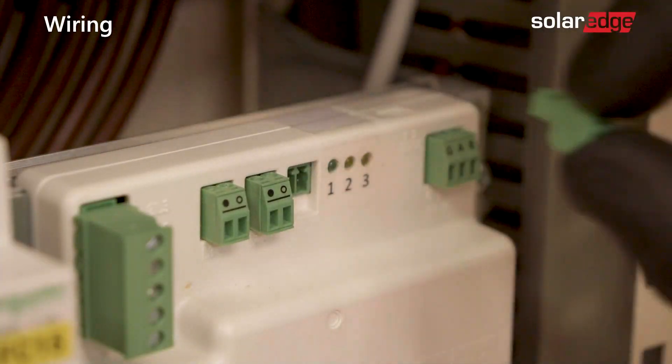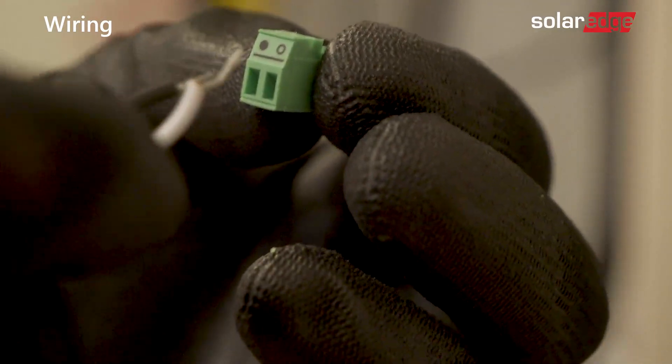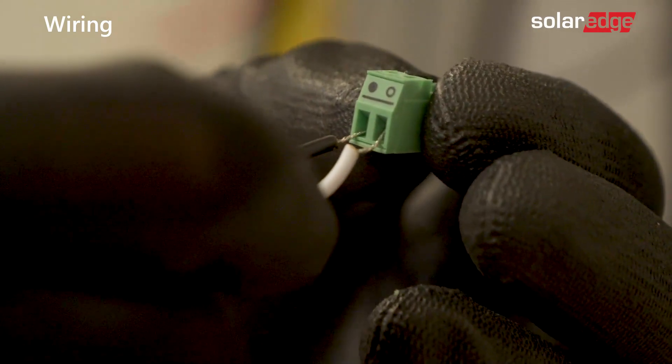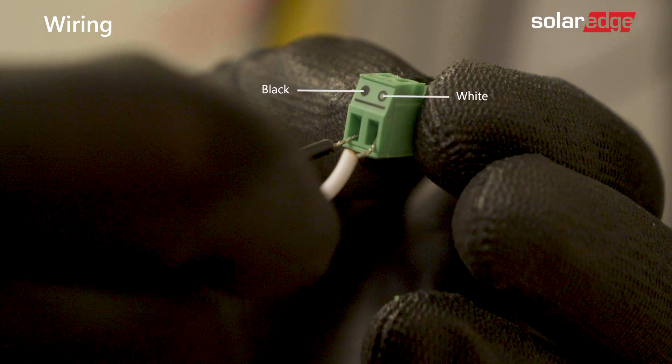Then, connect the CT wires to the three two-pin terminal blocks on the meter. Note that the black and white CT wires should be connected according to the dots printed on the terminal block.